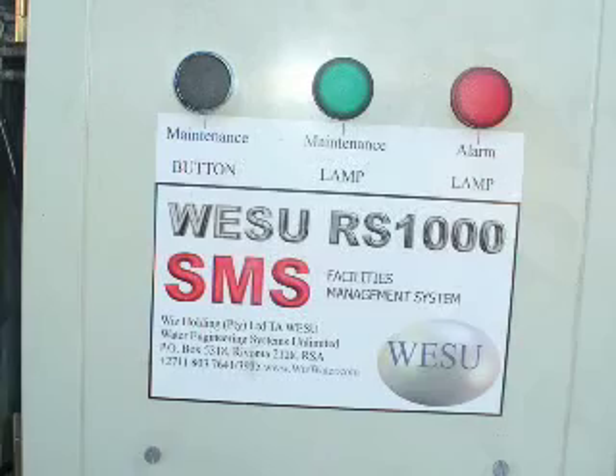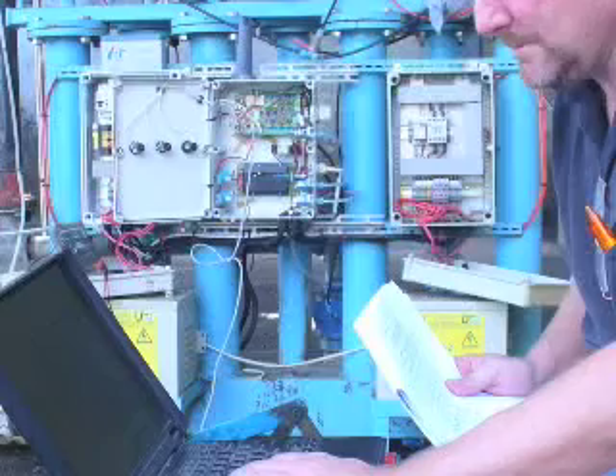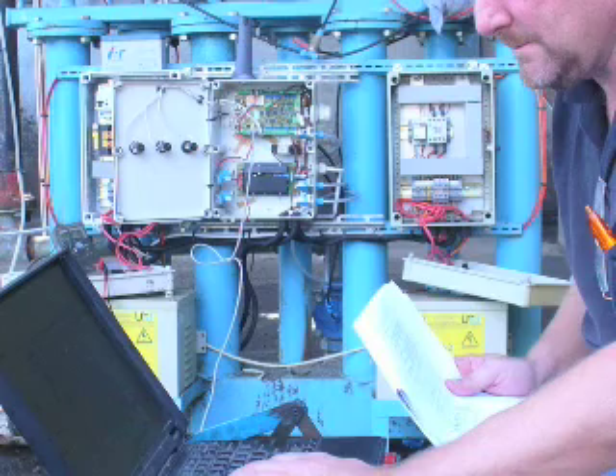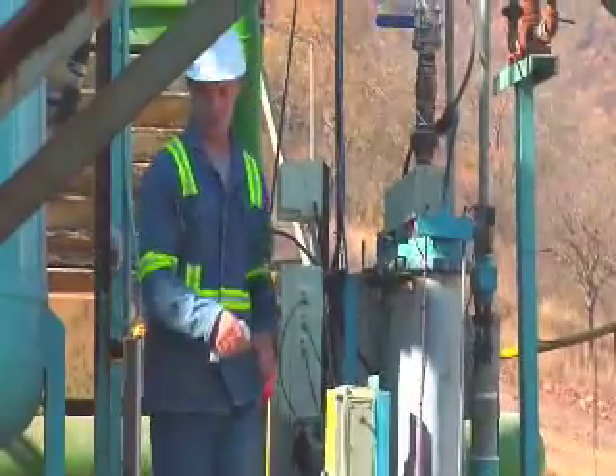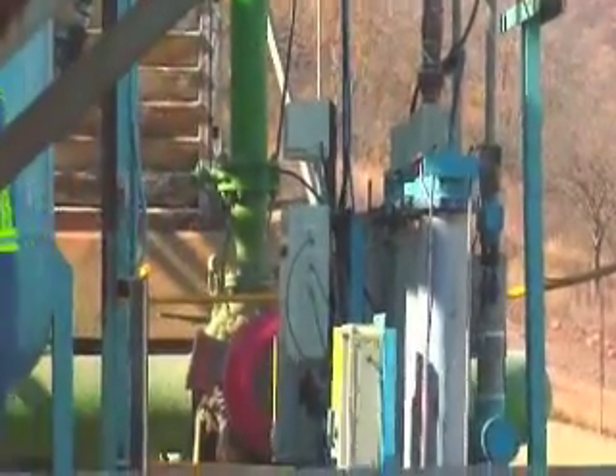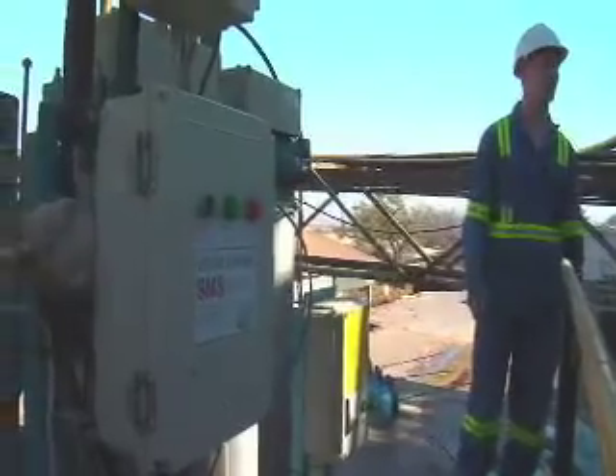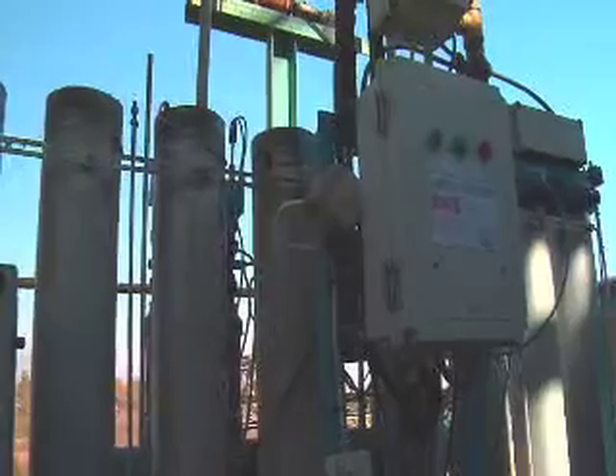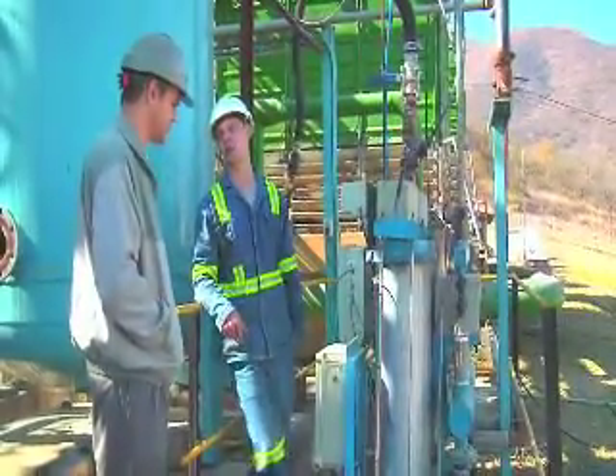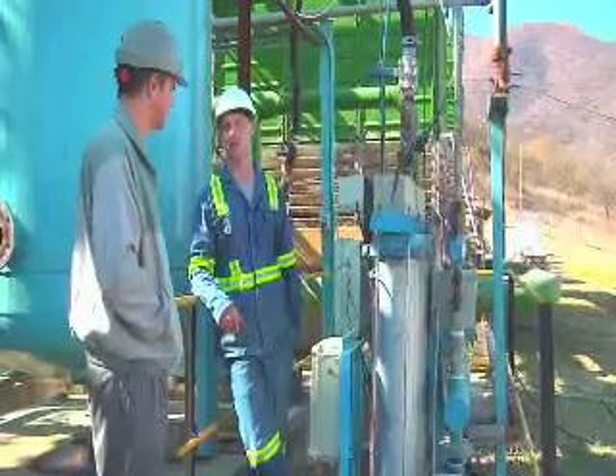From an operational point of view, as a guy who has to keep the plant running, I can tell you it's working. The WESU system has an SMS system that gives you a warning if any parameters are out of the required range. So I'm getting a pre-warning, so when my shift foreman phones me to tell me there's a power problem, I could tell him, okay, you've stopped at that time, you had a power failure, how's it going? So I'm sort of pre-warned and I have more insight, so they find it strange that I know so much about what's happening on the plant. So yes, it's an additional benefit.